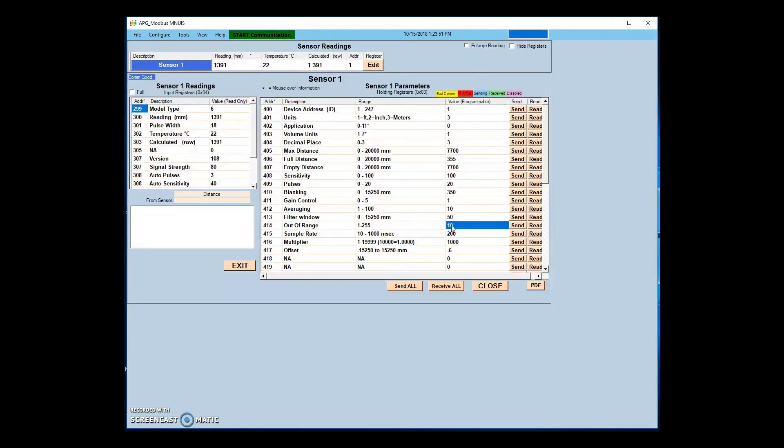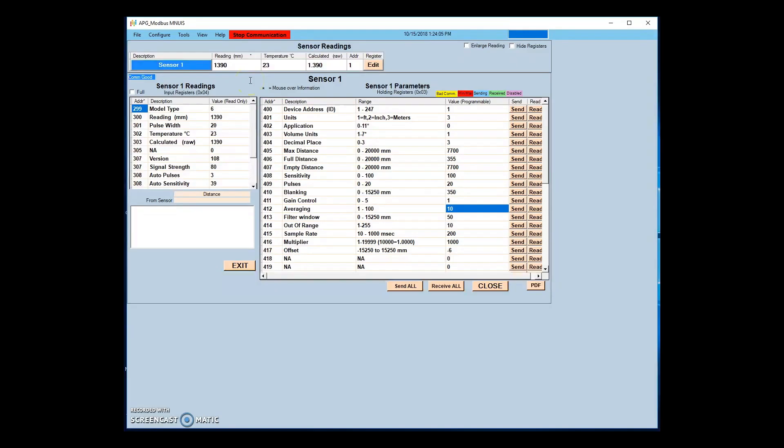The out of range value determines that 10 readings outside of the filter window must be received before the new readings will begin to be received into the averaging buffer. With these settings, it takes approximately 3 seconds for the sensor to respond to a new target.